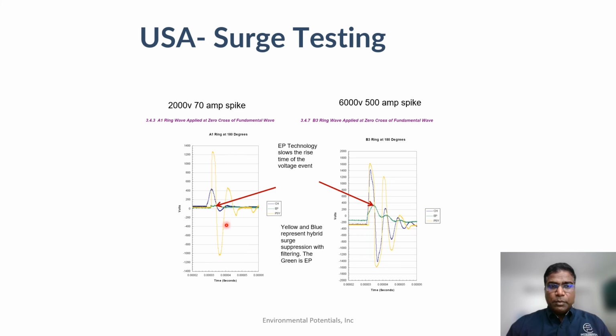See the yellow and blue lines - they're still left over with residual surges, what we call let-through voltage. This is the ringing noise, the negative peak and the positive peak. This is what affects the capacitance of your system, substantially decreasing the value of the capacitor in any electrical equipment, and then it affects the performance of the system.